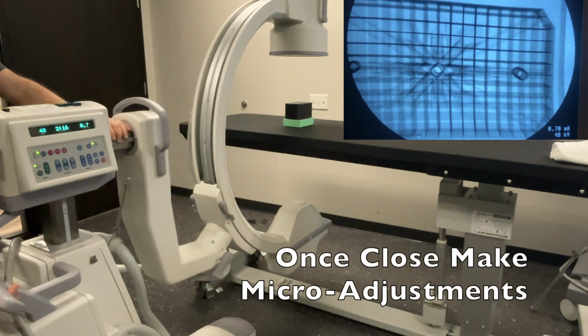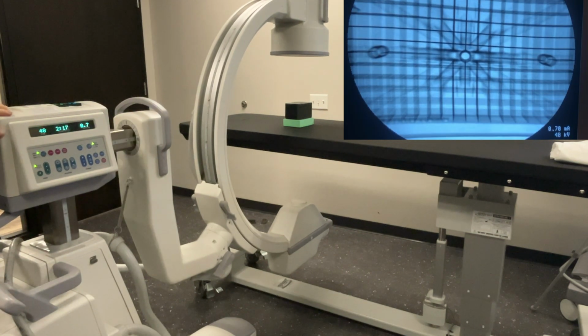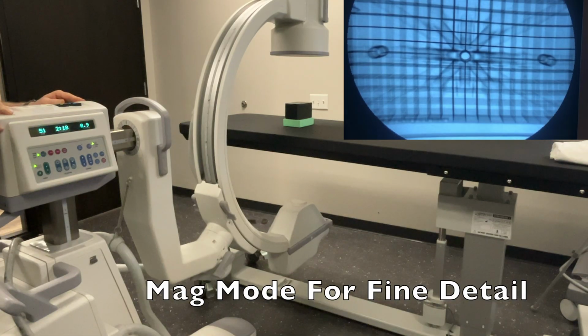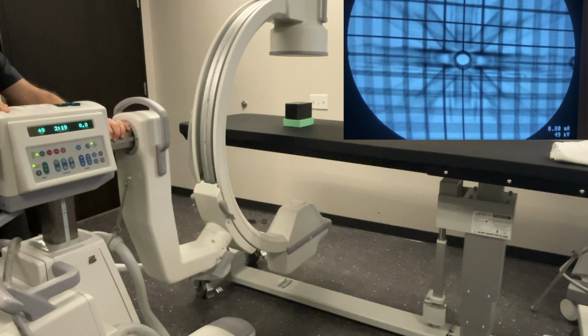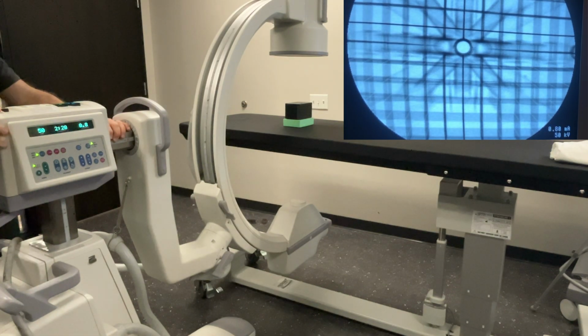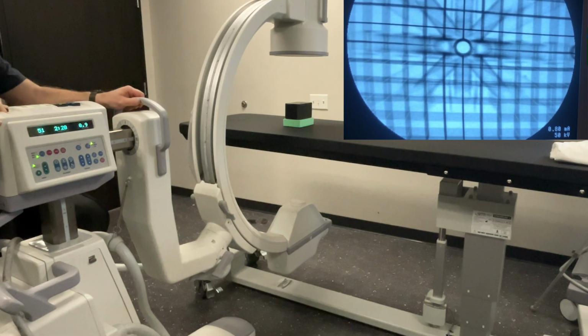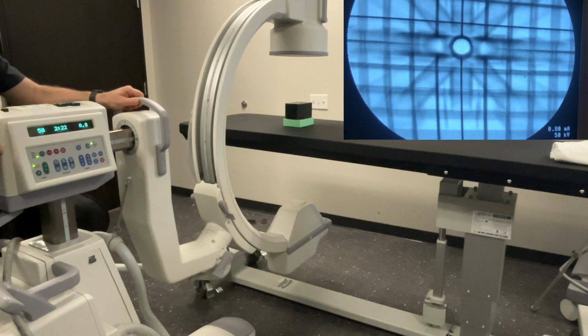After a couple of similar micro adjustments, we can then apply magnification to check for fine detail. A faint double shadow appears, but since the circles are off center, we know this is a centering issue, not tilt. With one final correction, we are able to demonstrate a properly aligned image with perfect circles.